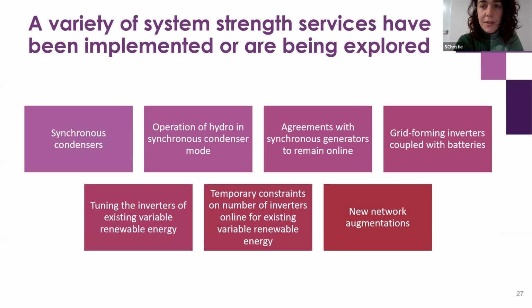We have temporary constraints on the number of inverters online for existing variable renewable energy. This is another one which is not going to provide the full amount of system strength required, particularly if we're using fault level as a proxy, but it's something we can do to reduce the number of issues on the system. It's important that the inverters are actually offline for this to work, not just about the renewable energy not providing any megawatts - the inverters need to be offline.